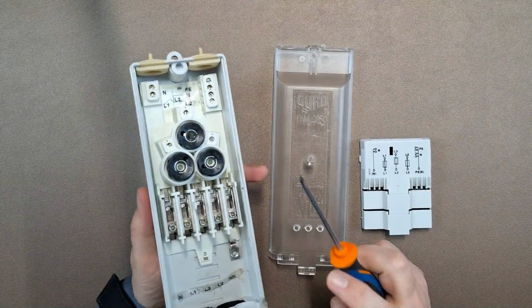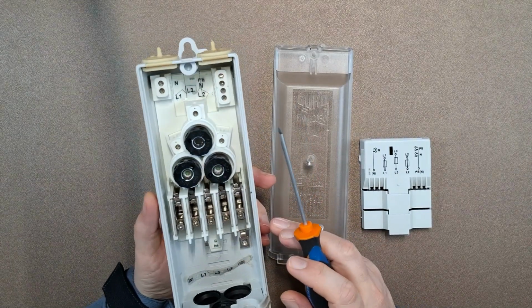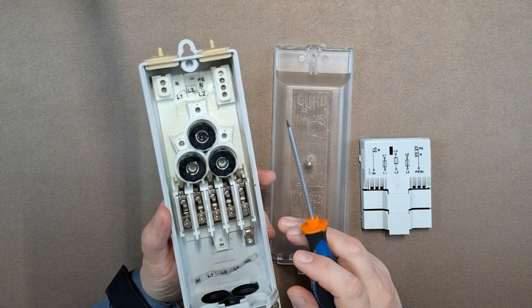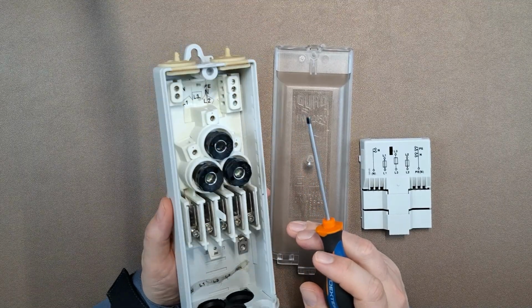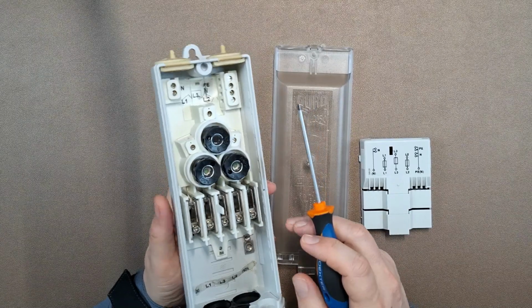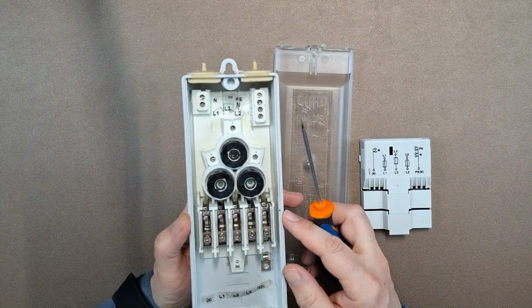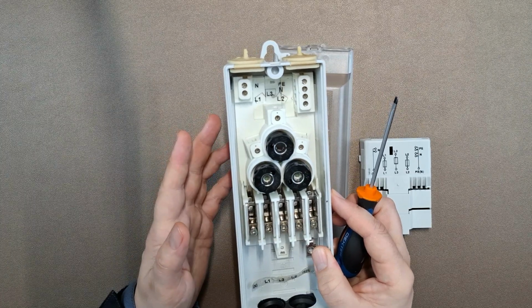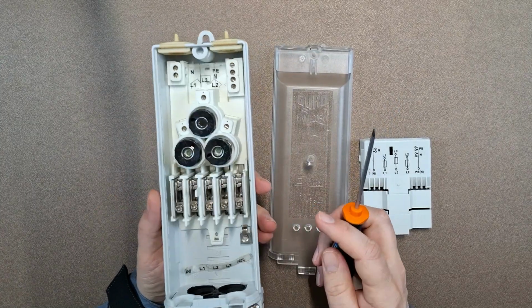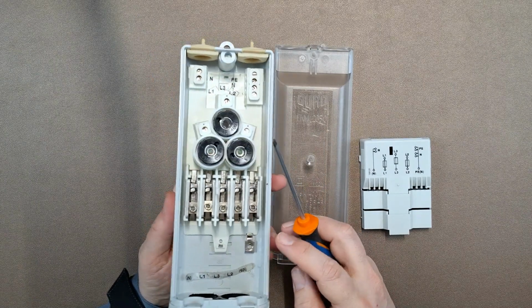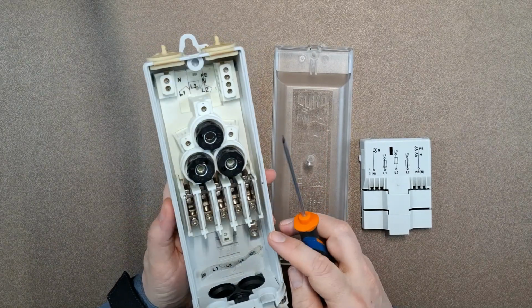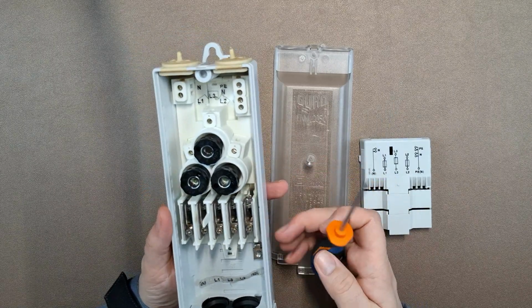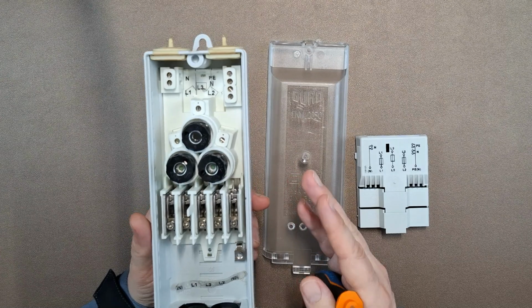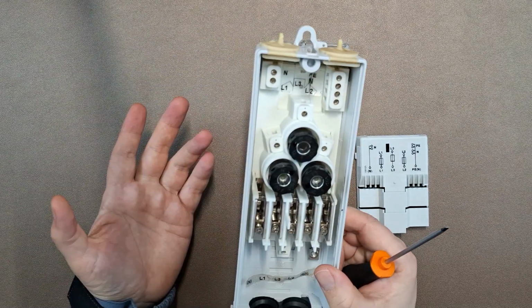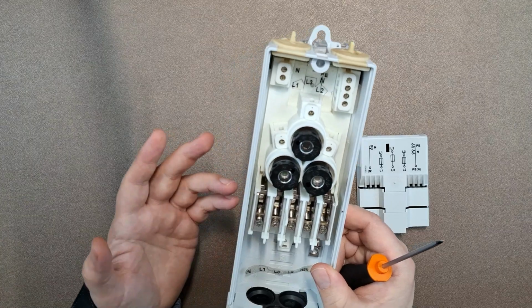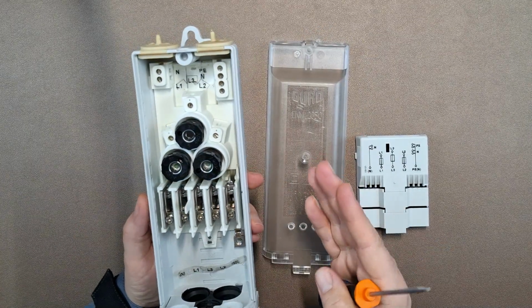My opinion: in harsh conditions near the sea, where it's minus 50 degrees Celsius in winter and the humidity is high, then yes, this solution makes sense, or if the customer has the budget. In moderate climates, you can just install regular circuit breakers inside the pole, even in a simple plastic box, and wire it up the usual way. It will last as long as the lighting pole itself. You could even skip the circuit breakers, but then, if there's a short circuit or overheating, the whole line will shut down.